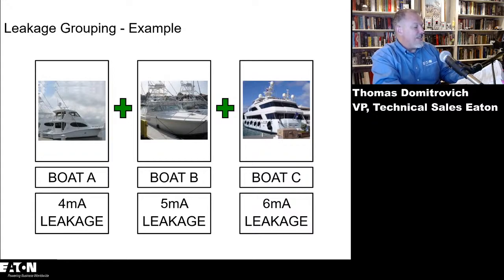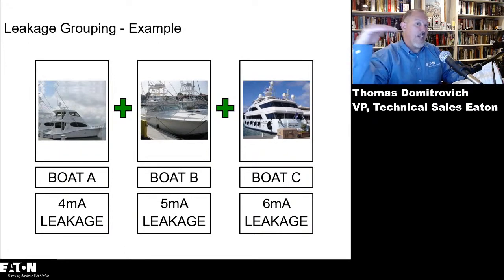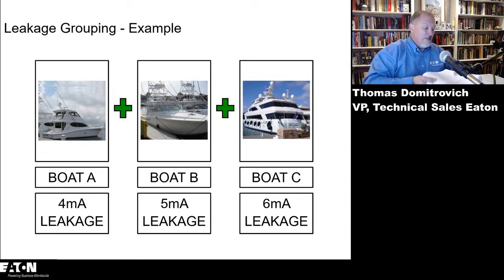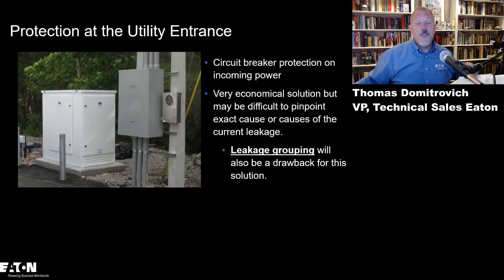Service equipment shall disconnect when the water level reaches the height of the established electrical datum plane. What that tells me is you need a float level out there, and it needs to be programmed or set so that you have it established at the electrical datum plane, and when the water level gets higher than that, you need to kill the service. That I don't believe anybody has done. I've not seen it, and when I read that, I was thinking, boy, I don't know how an electrical inspector would make that happen. Maybe it's done at some of these wastewater treatment plants and things of that nature. I don't know, but suffice it to say, that is probably an area that I don't know if anybody is doing that.